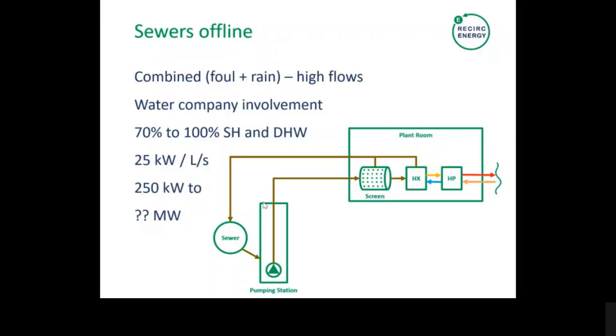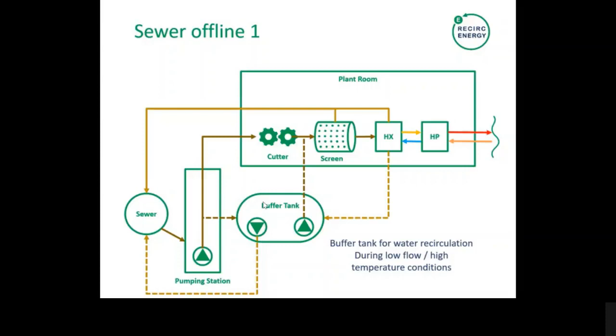One is where there's a simple pumping station, a buffer tank that can be used to recirculate the wastewater, which can be really important for periods of low flow and high temperatures. So we can use that wastewater more than once through the heat exchanger to achieve an overall higher delta T and actually get more heat out of the water per unit volume of water. But again, some form of cutter there or macerator screen before the heat exchanger, or in some cases a self-cleaning heat exchanger, which requires less upfront pre-treatment.